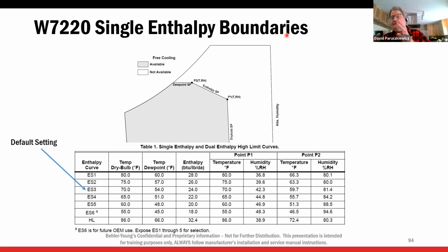Now you look on the psychrometric chart, and enthalpy is a combination of temperature and humidity, or total heat content. So it means at higher temperatures, I have to have lower humidity. At lower temperatures, I can have higher humidity. So it's looking at a combination. So we always set everything to D in the old school economizers.